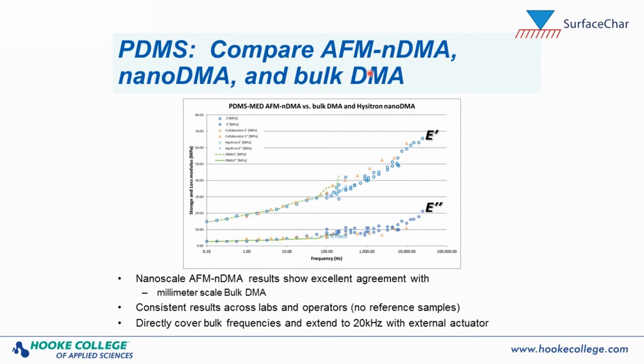And so here what we have is a plot of the storage modulus and the loss modulus on PDMS as a function of frequency. And so what we can see is if we focus on the AFM nano DMA measurements, which are in blue here, and compare them with the bulk DMA measurements that are the green line, we can see excellent agreement between the millimeter scale bulk DMA and the AFM nano DMA, which is on a length scale of about 10 nanometers. There's also some data in here from a collaborator on their own system in their lab, which are the spots in orange, and we can see that there are very consistent results across the labs and operators for these moduli.